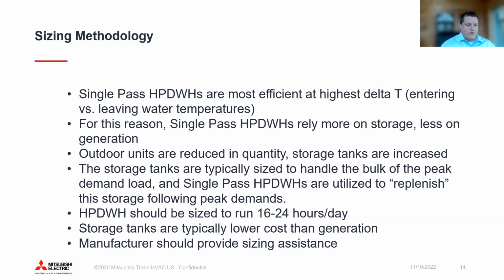Just to throw out a rule of thumb, and it's not perfect, obviously don't design by this, but just to give you an idea: if your boiler is typically, let's say, 1 million BTUs, and you would typically have, let's call it, 200 gallons of storage, what we would do is basically flip that on its head. If you were going to take that same 1 million BTUs of plant and try to match that with a heat pump today, it would just be way too expensive. So we really rely on storage to ride through the peaks and provide a more energy efficient system to the end user. Because of our average COP and things like that, if we were to take that standard 1 million BTU boiler design, we would probably be about 1/3 of that for the heat pump plant.